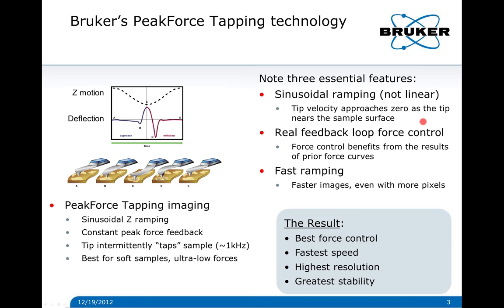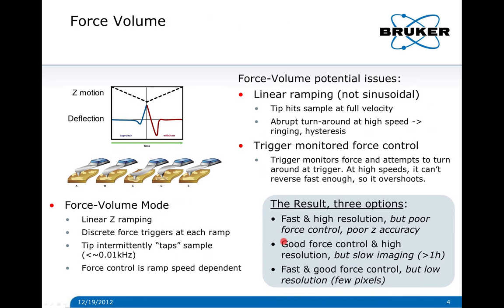Key features of this technique are that the ramping is sinusoidal, unlike force volume's linear ramping. The tip velocity approaches zero as the tip nears the sample surface, which helps with the feedback. The feedback is directly on the force, and it benefits from results from prior force curves because adjacent curves are very similar. This enables really fast ramping, which gives faster images even when we add many more pixels. The result is much better force control, faster speed, higher resolution, and excellent stability.